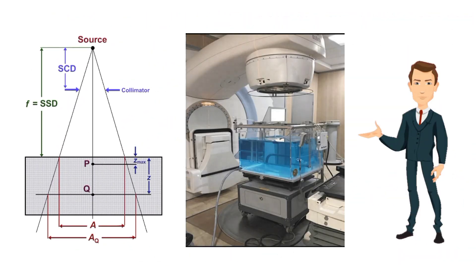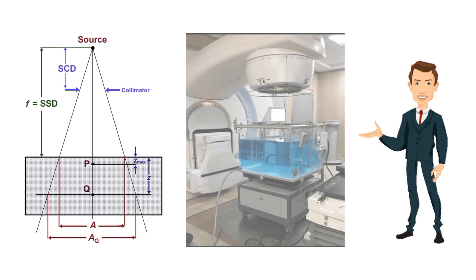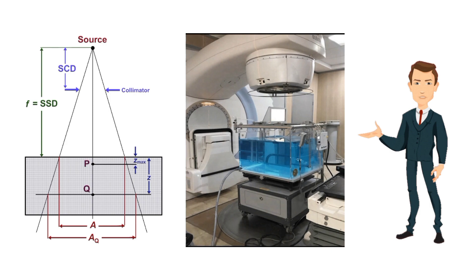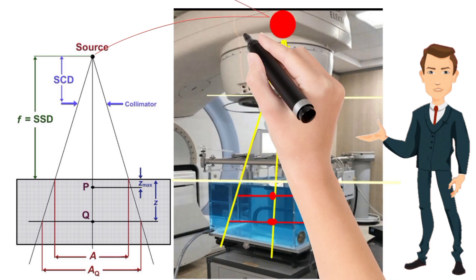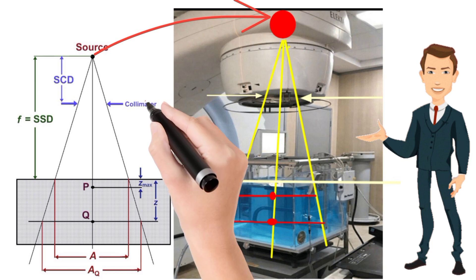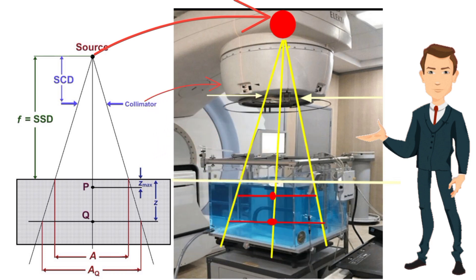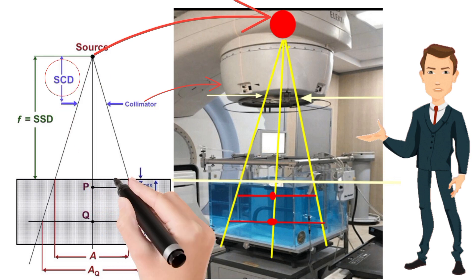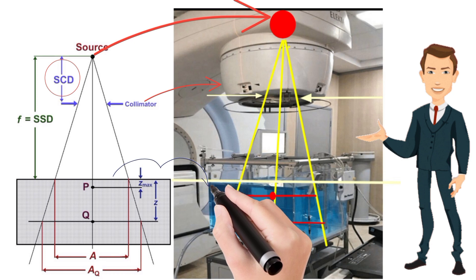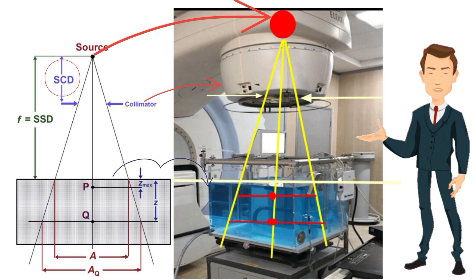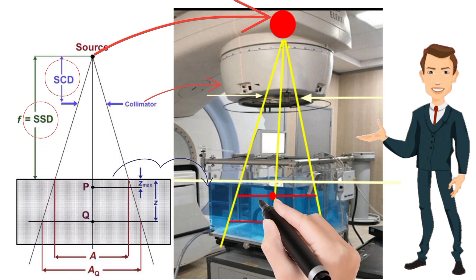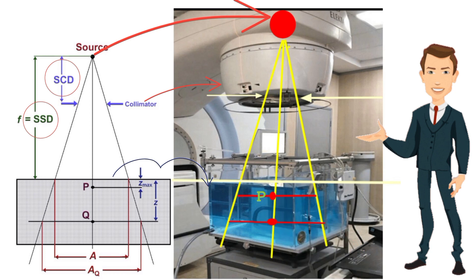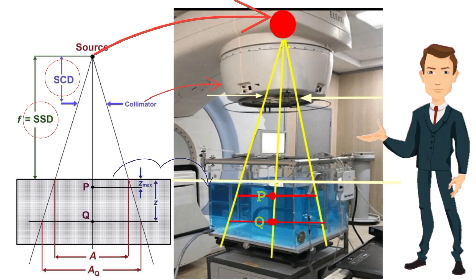We understand this ray diagram comparing it to a setup where a water phantom is placed under the head of a medical linear accelerator. This is the point source emitting photon beam. This is the collimator which helps collimate the beam. The distance between source and collimator is called SCD. The distance between source and the surface of the water phantom is called SSD. This is point P at depth D max, the depth at which maximum dose is deposited. This is point Q at depth Z inside the phantom.